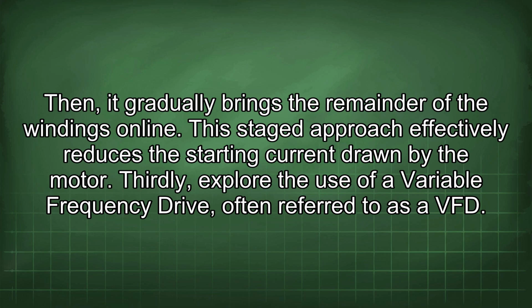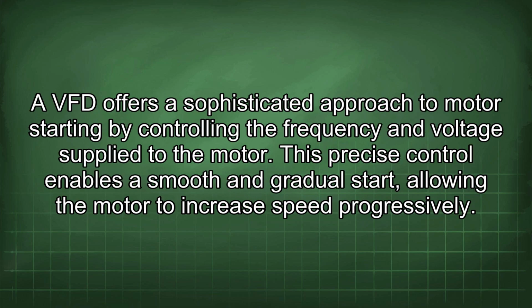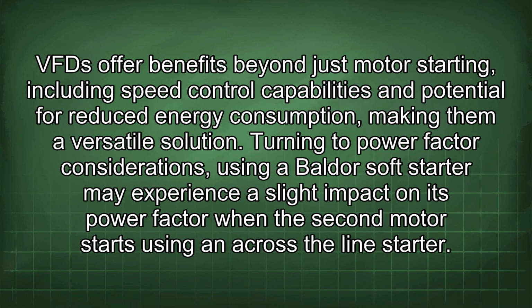Thirdly, explore the use of a variable frequency drive, often referred to as a VFD. A VFD offers a sophisticated approach to motor starting by controlling the frequency and voltage supplied to the motor. This precise control enables a smooth and gradual start, allowing the motor to increase speed progressively. VFDs offer benefits beyond just motor starting, including speed control capabilities and potential for reduced energy consumption, making them a versatile solution.